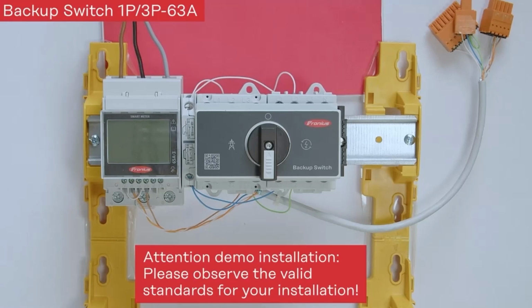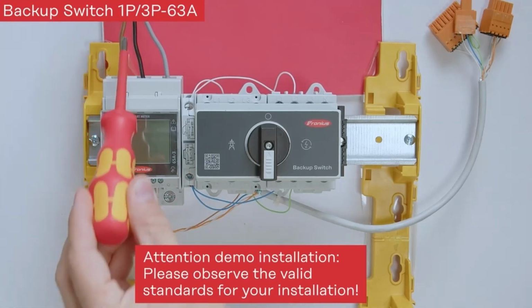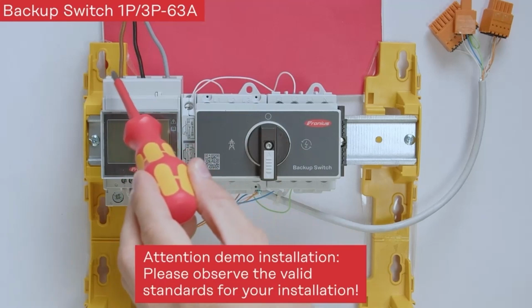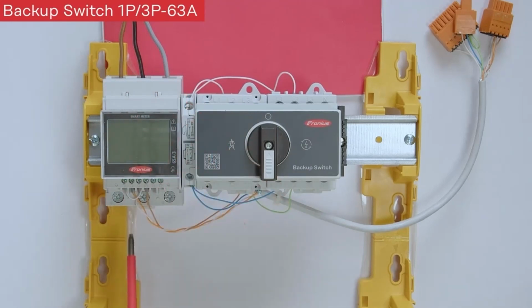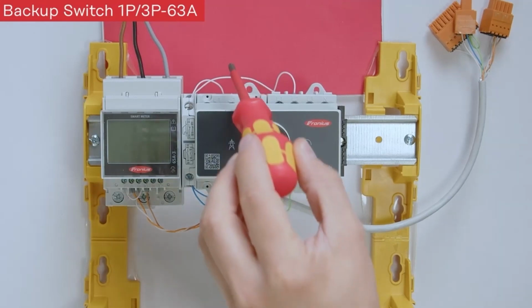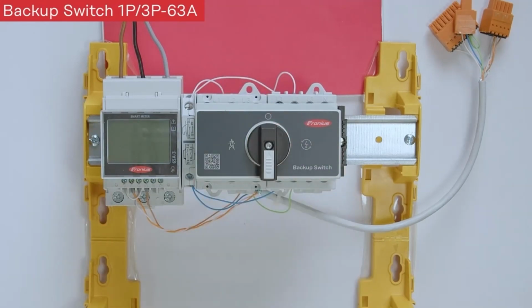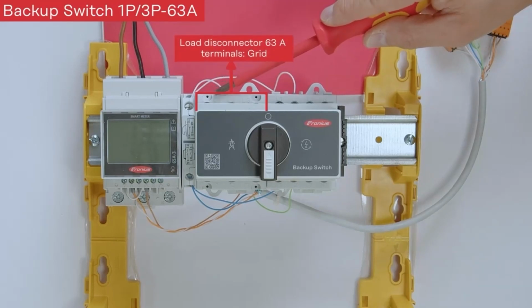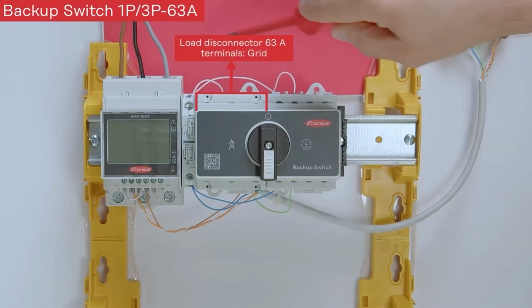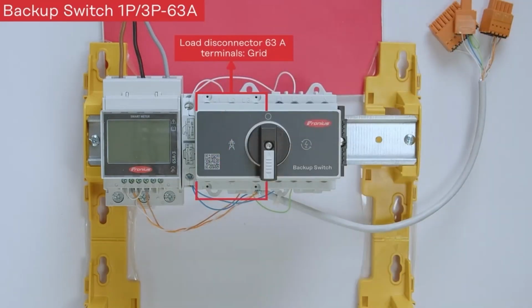On the top side here, you see coming from the public grid to your Fronius smart meter, three phases going into L1, L2 and L3, and exiting the Fronius smart meter on the bottom side. And then from the smart meter, you can go directly to the backup switch. On the backup switch, you always have L1, L2, L3, and then you go directly over the switch with your household loads and later on also to the Fronius inverter.